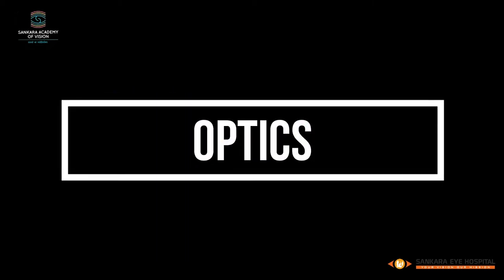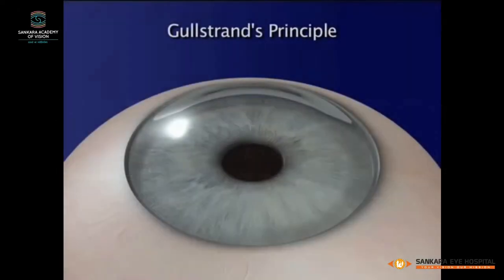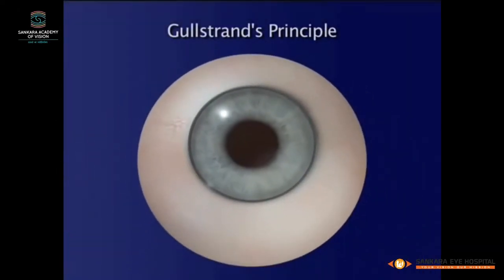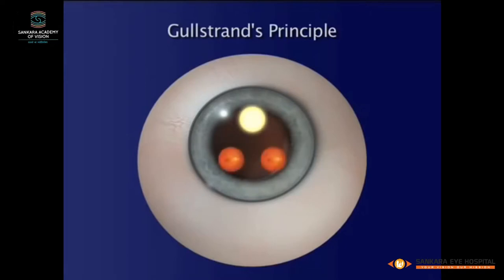The optics of the IDO is based on Gullstrand's principle that involves three separate beams that all pass through the patient's pupil. These consist of one illumination beam and two separate viewing beams, one for each of the examiner's eyes.